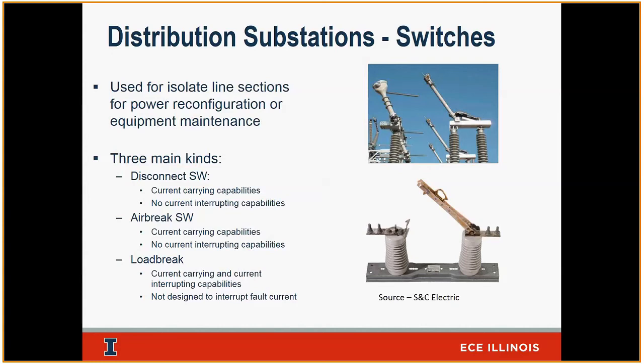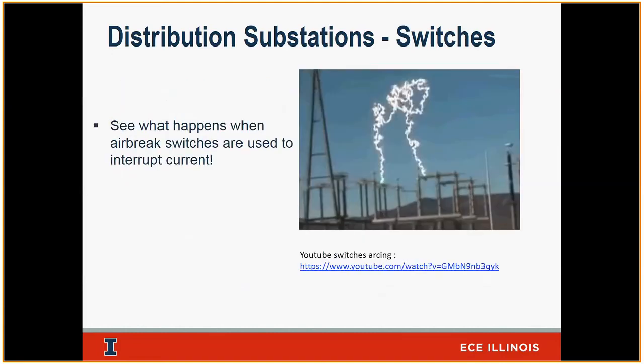First two, you don't open them up when there's current. You do not. Otherwise, you'll see a big arc. And I think I put a link there to what would happen if you do that, if you don't have the current interrupting capability. Again, because it's non-vacuum, it's air. That discharge will catch on fire, and basically it'll cause that arc. Could kill somebody. And that's exactly what would happen if you would open it when it's not de-energized. So typically you would really like to de-energize the 69 kV line from its source.